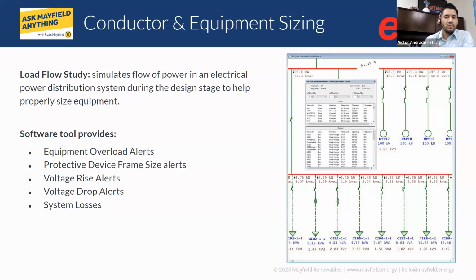Additionally, it also helps check. Once you perform the design and you want to do a quick check as part of this particular study, ETAP has an equipment evaluation capability that gives you an alert when the equipment, in this case, for example, a protective device, fuse, cartridge size, or frame on a low voltage breaker, is not properly set. There will be an alert for that. Additionally, if you run a load flow, it'll give you any voltage rise or voltage drop alerts. And this is very common, especially on large PV systems with a large DC collector bus. If you're not using the right inverter, you'll usually see a really large voltage rise, and that tends to cause all kinds of issues. So those are the types of alerts that you would be able to model and simulate at the design stage.